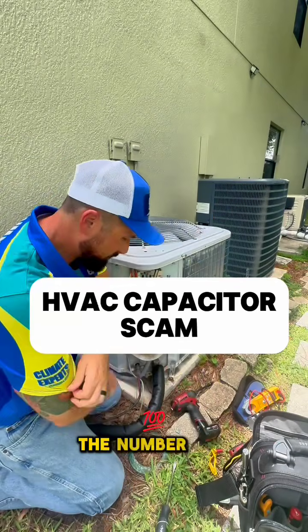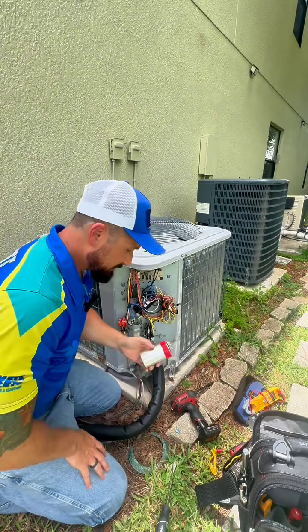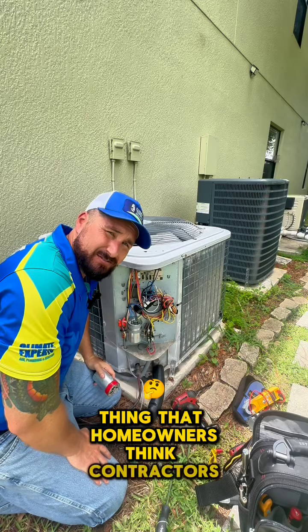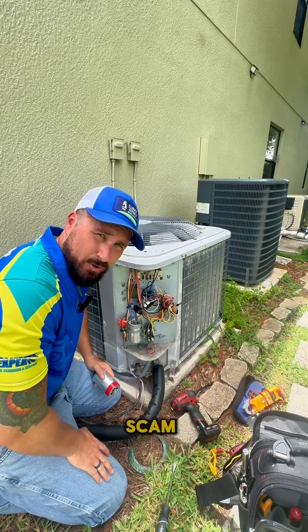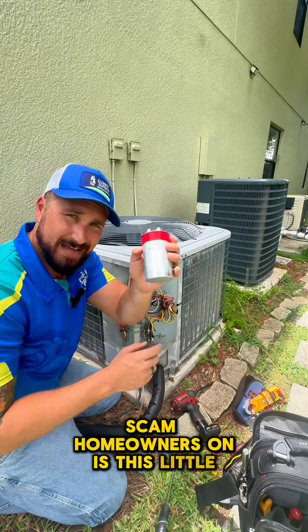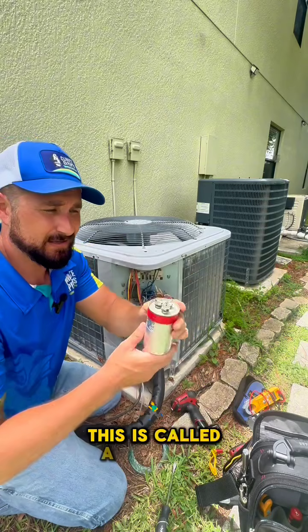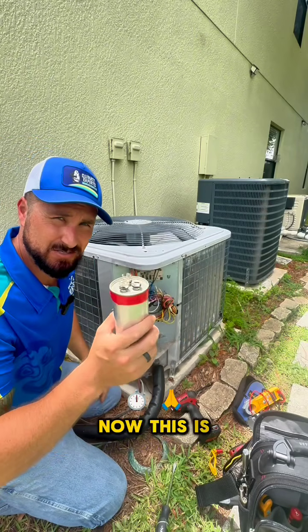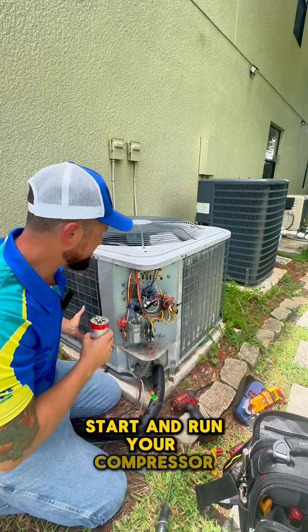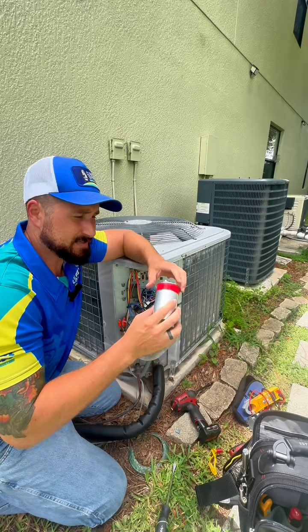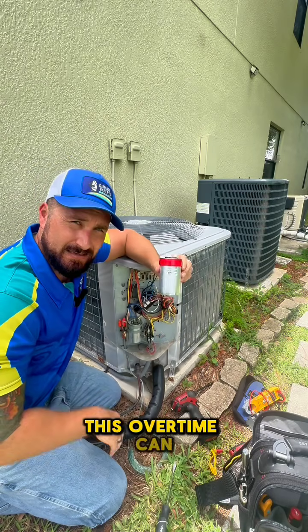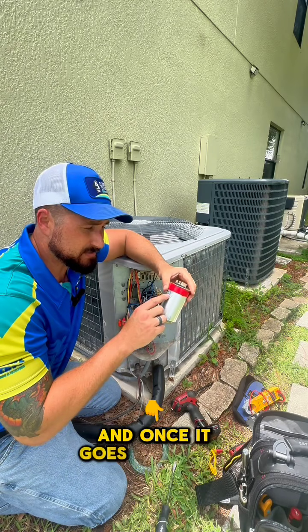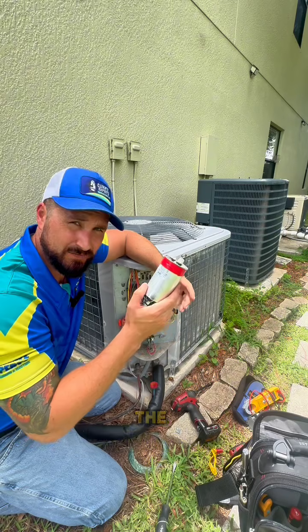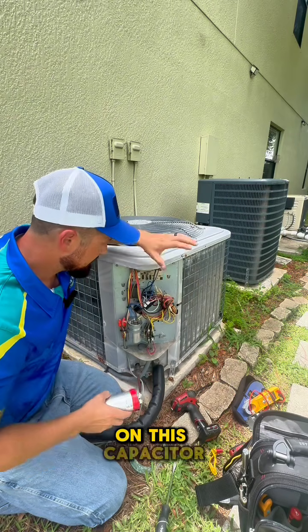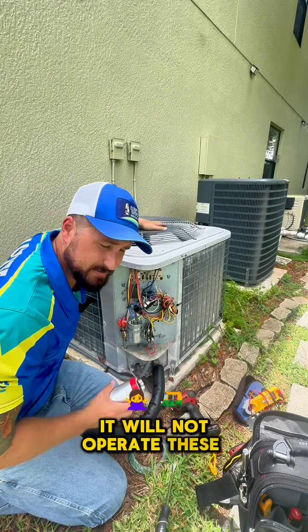Now, the number one thing that homeowners think contractors, HVAC contractors specifically, scam homeowners on is this little guy right here. This is called a dual run capacitor. Now, this is supposed to help start and run your compressor and your fan motor. This over time can get weak, and once it goes below its desired recommendations, the microfarads that are listed here on this capacitor, it will not operate these motors and this compressor properly.